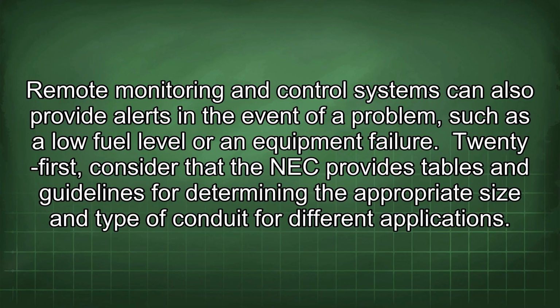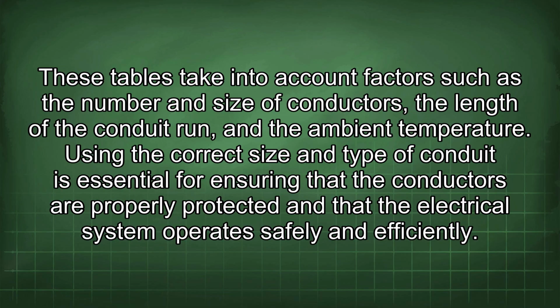Remote monitoring and control systems can also provide alerts in the event of a problem, such as a low fuel level or an equipment failure. 21st, consider that the NEC provides tables and guidelines for determining the appropriate size and type of conduit for different applications. These tables take into account factors such as the number and size of conductors, the length of the conduit run, and the ambient temperature. Using the correct size and type of conduit is essential for ensuring that the conductors are properly protected and that the electrical system operates safely and efficiently.